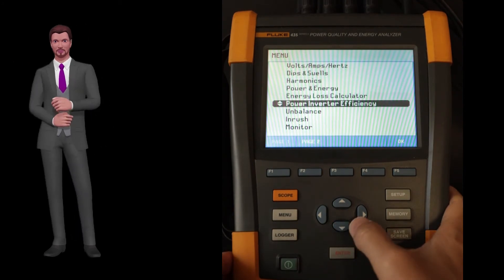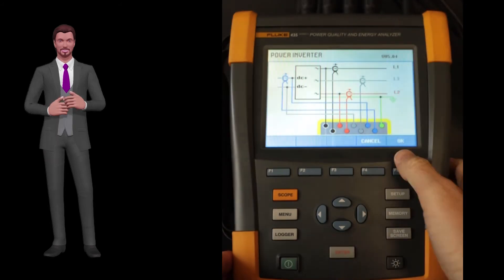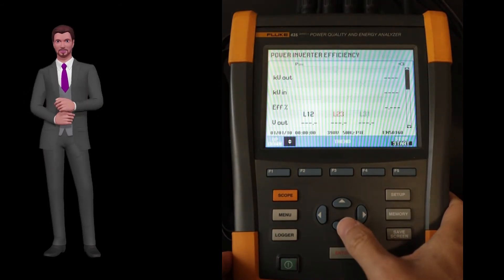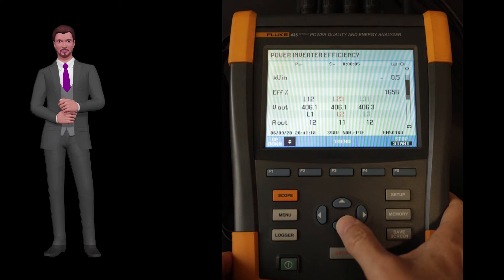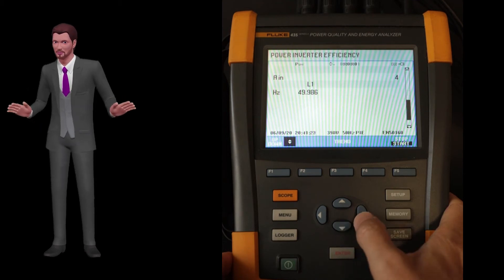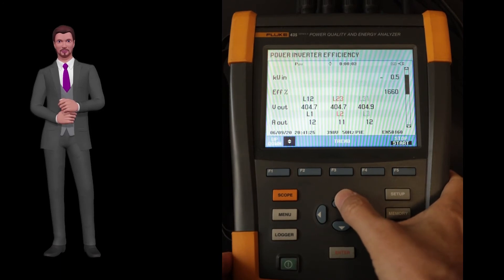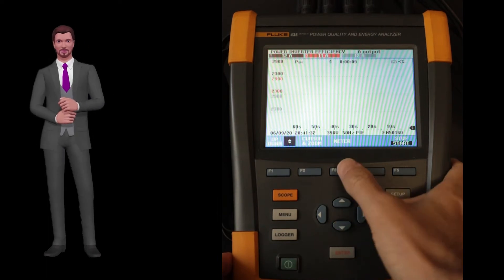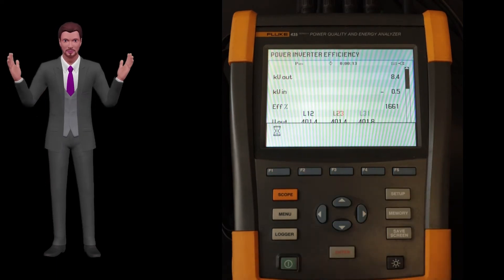The next function is the power inverter efficiency function. With this function you can measure the DC power at the input of the inverter and the AC power at the output, so the instrument can calculate and provide the efficiency of the inverter. It is very useful, for example, for photovoltaic installations. But remember: to measure DC power, you must use a current clamp that measures DC current, since flexible probes cannot measure DC currents.